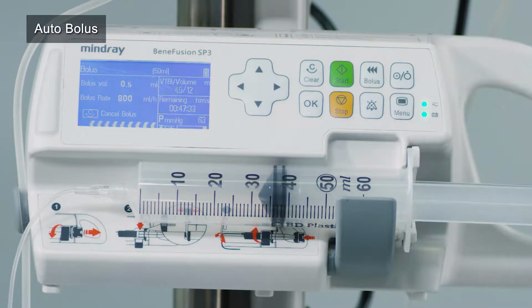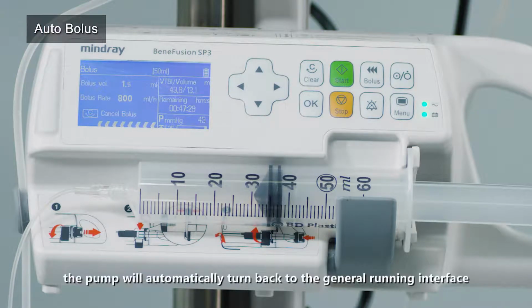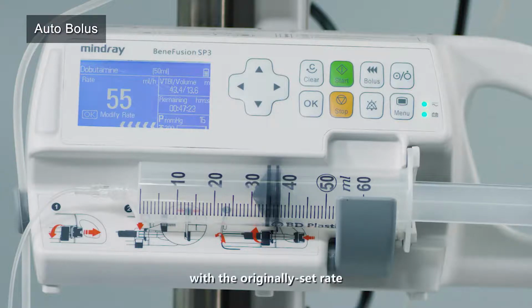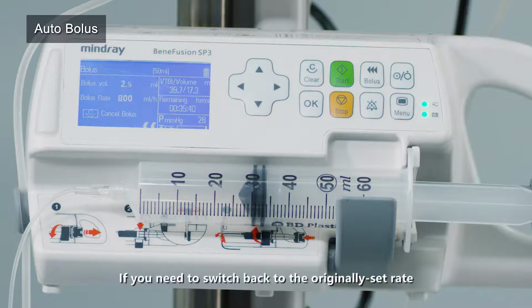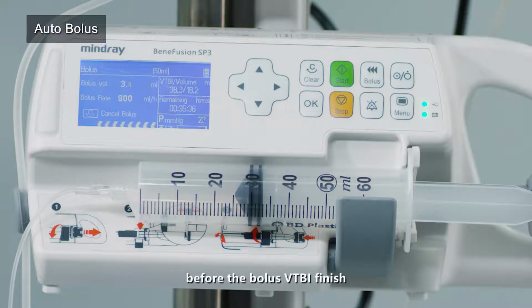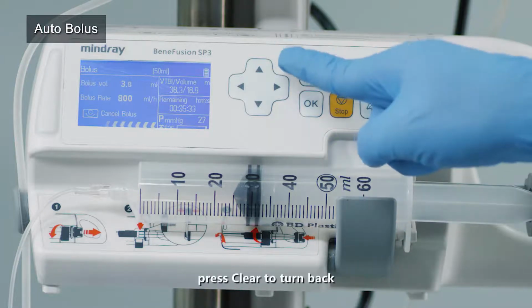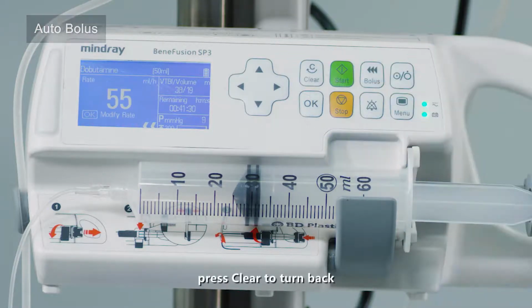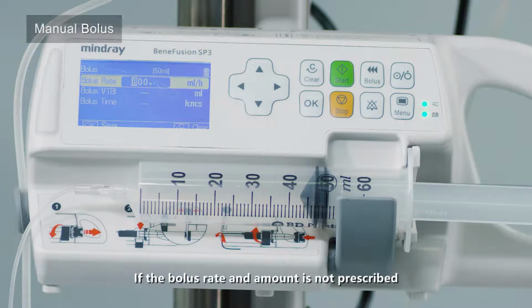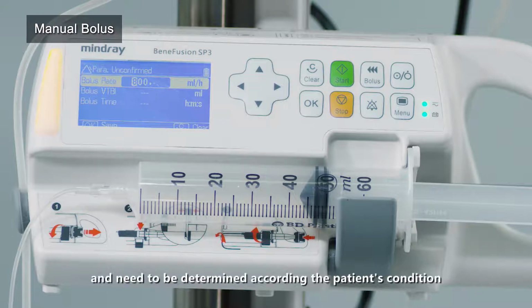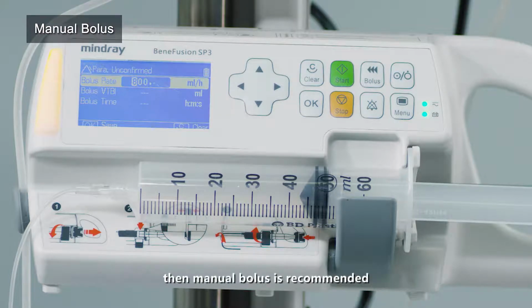the bolus. After finishing the bolus, the pump will automatically turn back to the general running interface with the originally set rate. If you need to switch back to the originally set rate before the bolus VTBI finishes, press Clear to turn back. If the bolus rate and amount is not prescribed and needs to be determined according to the patient's condition, then manual bolus is recommended.